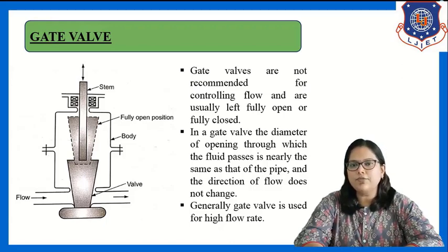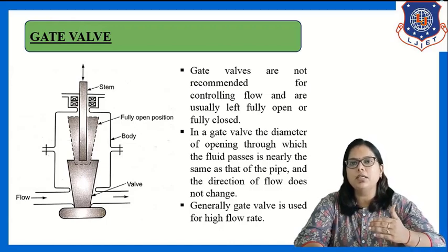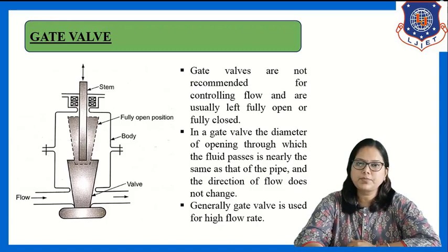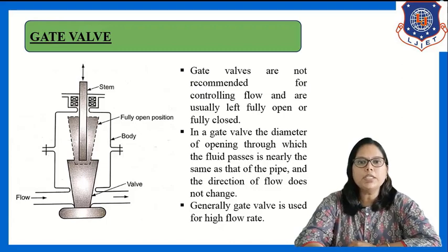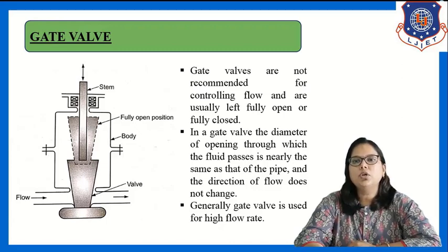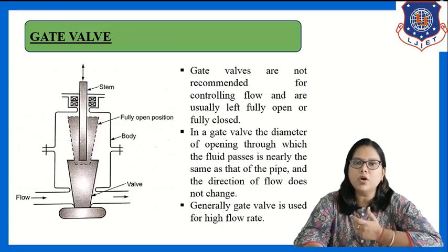Not used for controlling the flow, that means we cannot increase or decrease the flow rate with the use of gate valve. But we can stop the flow or we can continue the flow with the same flow rate. So, gate valve is mainly used in those applications in which we have to stop or continue the flow. It is not recommended for controlling the flow rate. That means it is usually left fully open or fully closed.